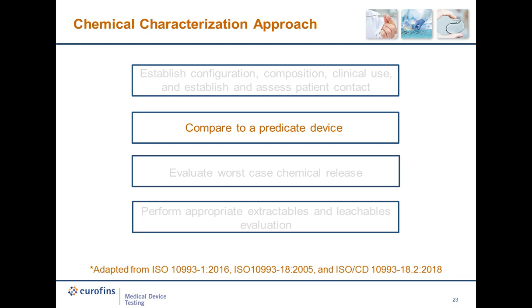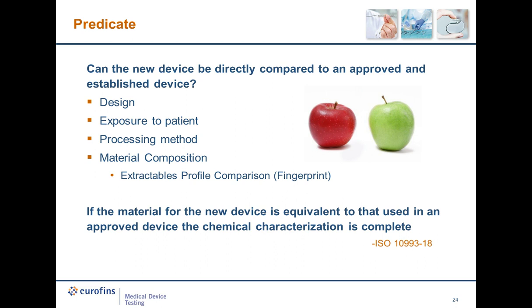After establishing the device, the first step or option in the chemical characterization process is a comparison to a predicate device. An appropriate predicate device is a device that has been approved and established to be safe for use. Equivalence between the new device and the predicate device is demonstrated through a comparison of the information that has already been gathered during the first step of the chemical characterization process. The purpose of this comparison is to determine if the safety risk of the new device is the same or less than the approved and established device.